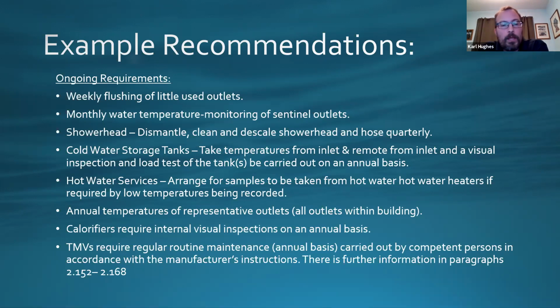Calorifiers, if they've got a hatch on the side of them, you would need to open them and inspect them internally to see what debris is in there and what the conditions are like inside. If you can't get inside them, what they recommend is you take a sample from the drain water for any debris or anything that you can see that could be causing any problems, and action accordingly.